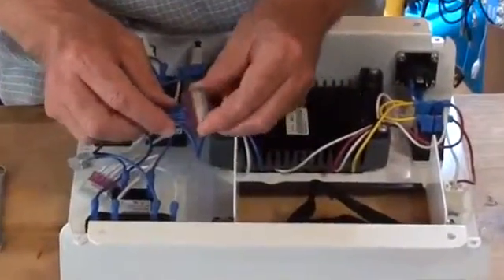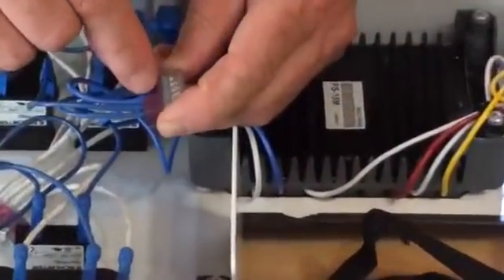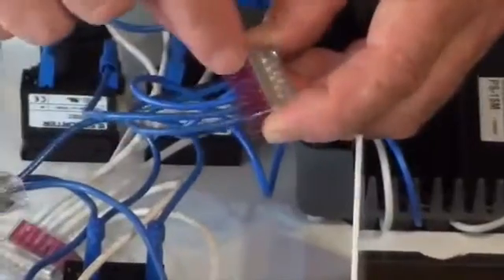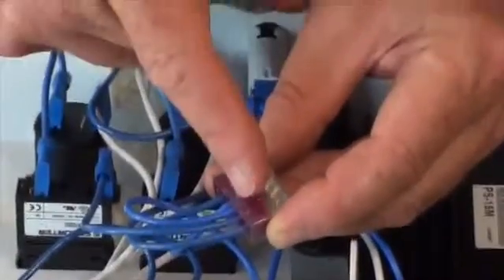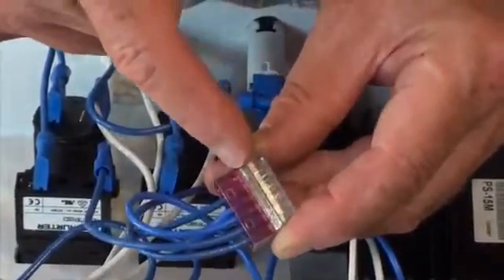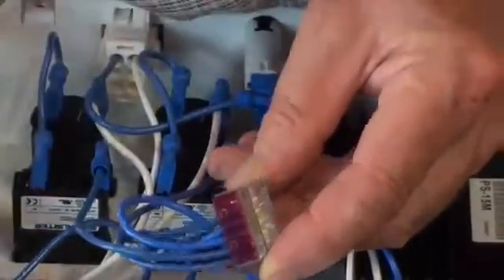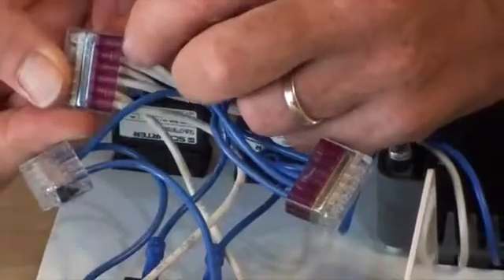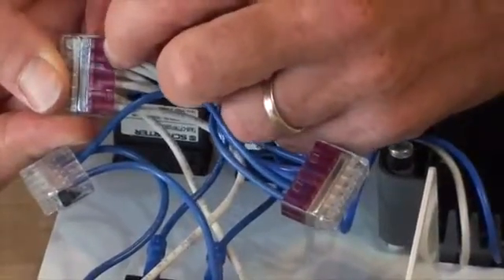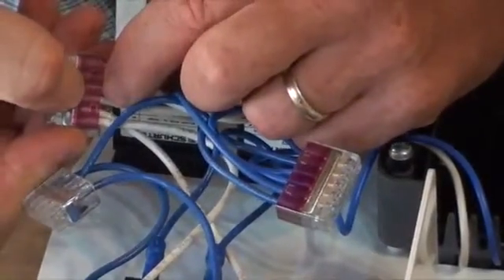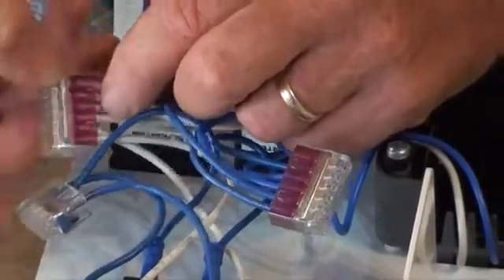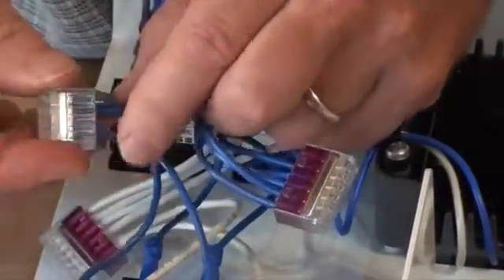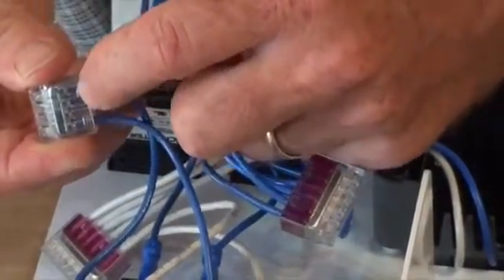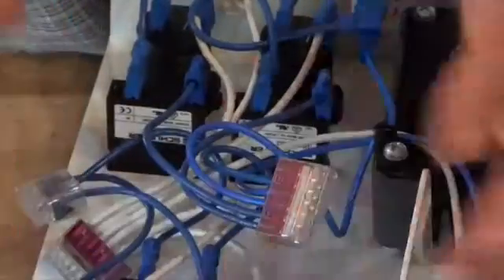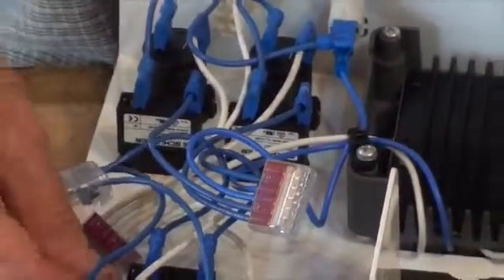You can check this by looking at the window. In the case of the positive wires, you'll see blue insulation going most of the way into the purple space on this connector, and the white insulation going most of the way into the purple space of this connector. So these are in a good quarter inch or more, which is excellent. They also did a good job looking through the window on this terminal block. Everything here looks really good.